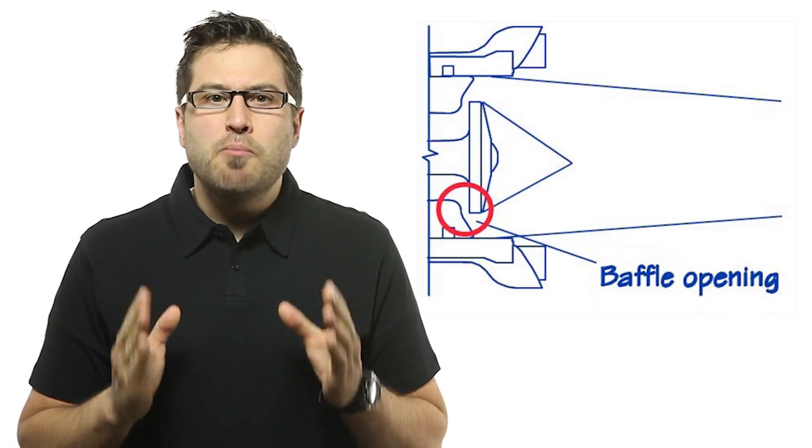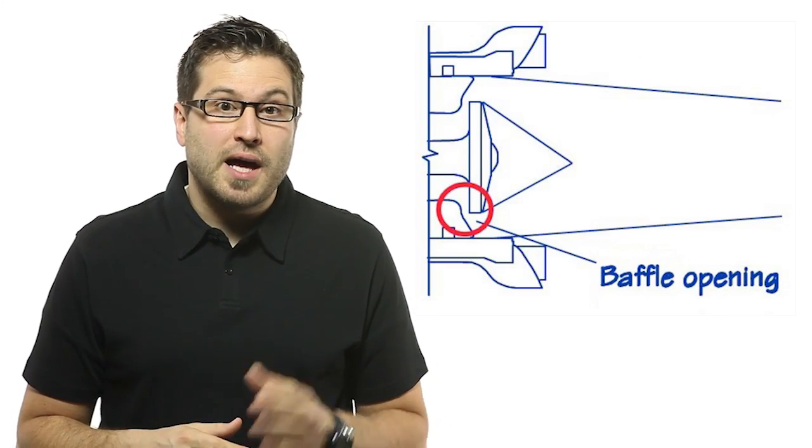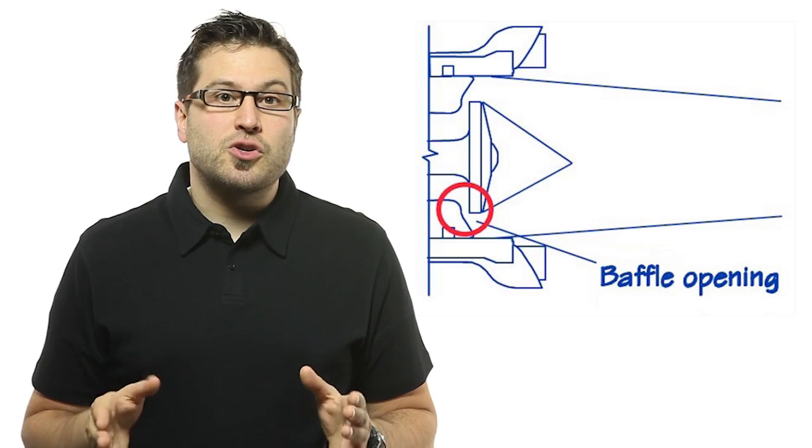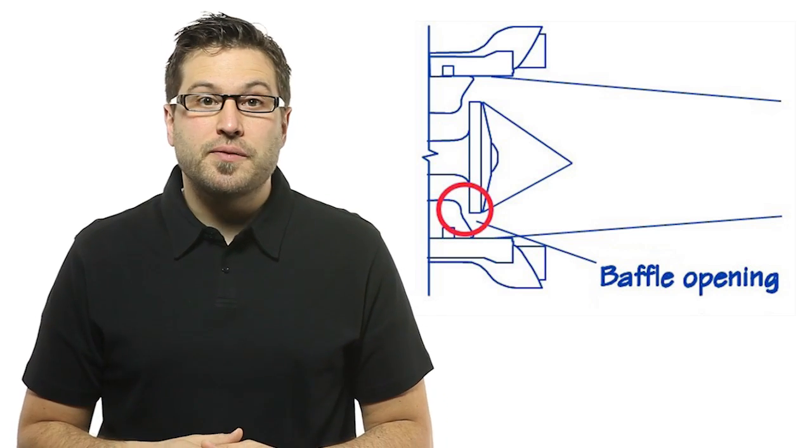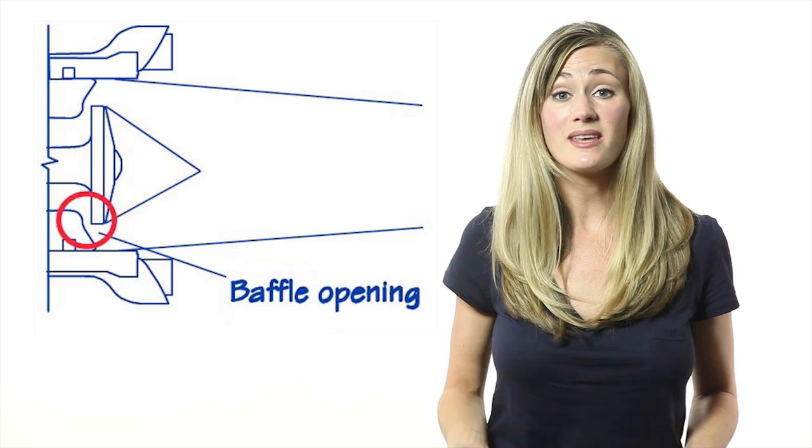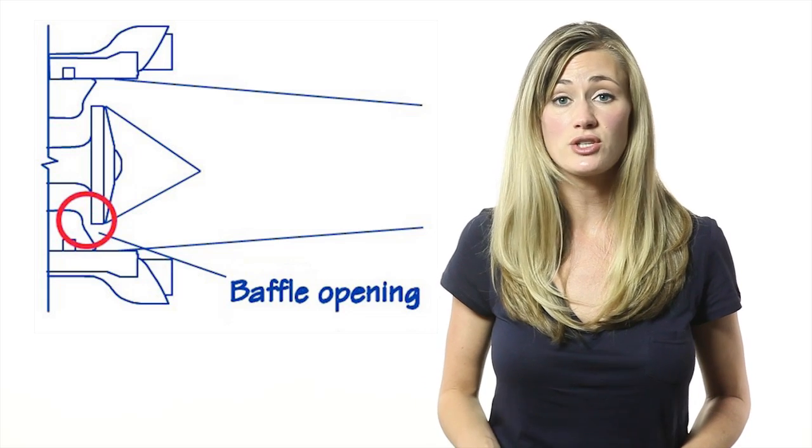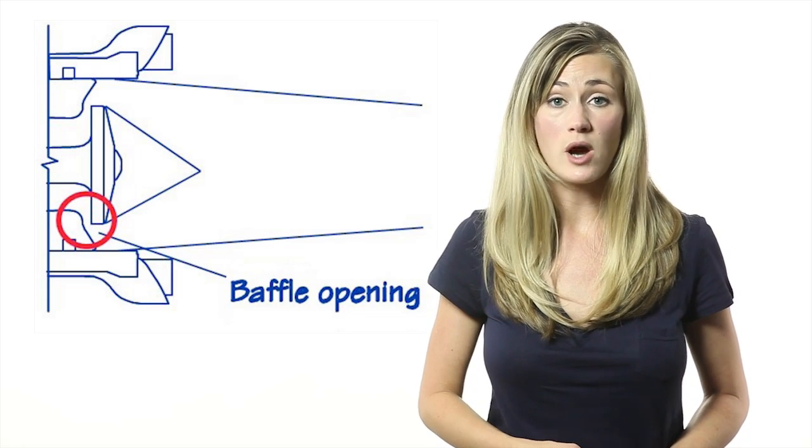The spring allows the baffle to open more if there's an increase in water supply to the unit, maintaining the pressure while allowing more water to flow through. Their main advantage is that the adjustable opening provides a steady stream flow pattern with varying water supply conditions.